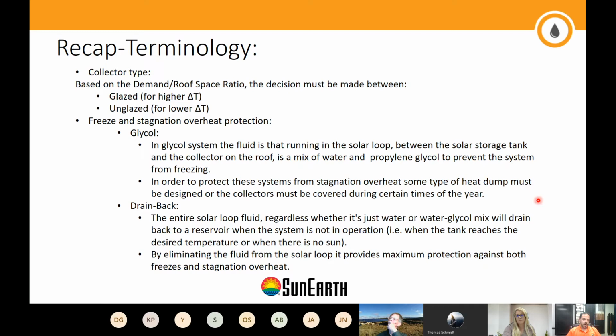For the drain-back system, it's a little different: the entire fluid in your solar loop drains back into the drain-back reservoir once you reach a certain high or low temperature limit, handling both freeze protection and overheat protection. It's simple—once you drain the entire loop into the reservoir, all that's left on your roof is some aluminum, some copper, and some glass.